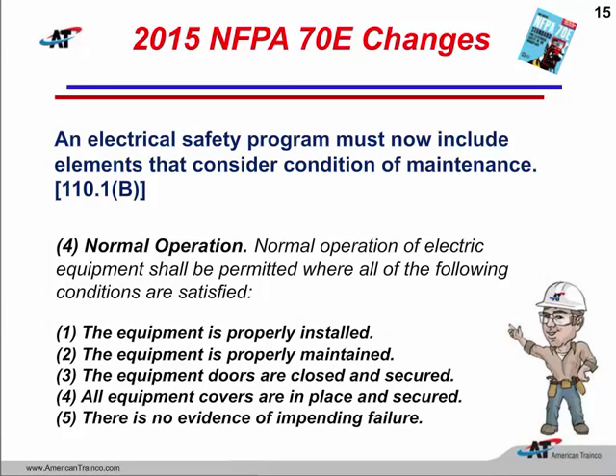As I stated before, the electrical safety program now has to include some condition of maintenance for the electrical equipment that we're about to approach. So notice it says normal operation. Well, we got to get a handle on this. Normal operation of electrical equipment shall be permitted where all the following conditions are satisfied. Well, the equipment is properly installed. Most electrical equipment that I encounter has been properly installed. It was installed under the National Electrical Code of the cycle that the installation took place. The installation is usually inspected. A permit was pulled, and some outside authority having jurisdiction came and stated, yes, that was properly installed. So that one can be handled pretty good.